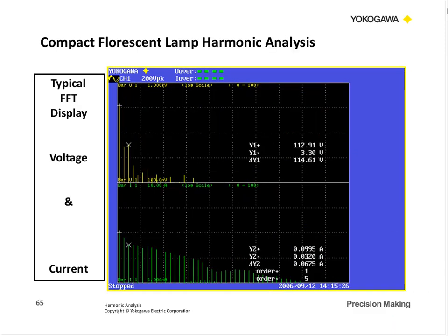So here's our harmonic spectrum of the voltage and the current. Again, you'll see that current goes way out in the harmonics, but the voltage drops off pretty quick, so we're not going to have much harmonic power. And again, I set the cursors just at the first and the fifth because I had my first fundamental right here. Third, the fifth was kind of high, so that's why I chose that one.